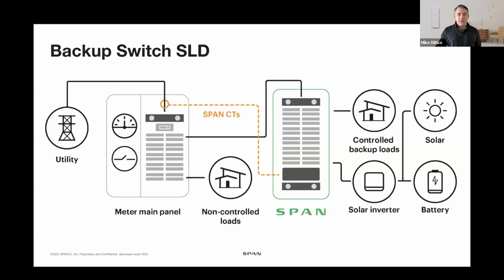You've got your Tesla backup switch here in your meter main, and you're going to have some non-controlled loads that stay in your meter main. You're going to add those SPAN CTs shown here in yellow, and you're going to add that SPAN MLO 24 as your sub panel. By doing that, all of those loads in the SPAN 24, up to 24 loads, can now be controlled.